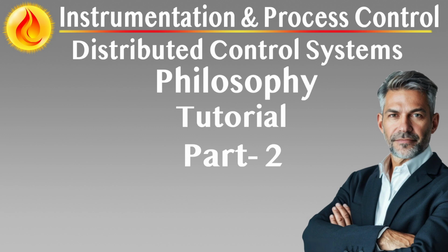Redundant Operator Workstations, OWS. Each OWS is configured in active-active pairs with real-time mirroring. In the event of failure, a seamless switch ensures uninterrupted control. These workstations run on industrial-grade computers or virtual thin clients connected to high-availability back-end servers.